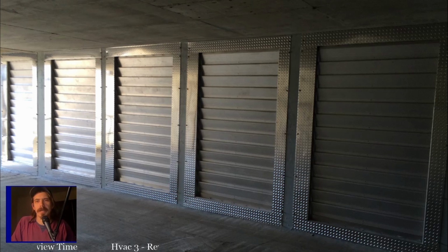So that circuit has to be energized for a split second before the time delay opens the circuit on the fan. That's generally how you can tell if the fan control is no good: you'll turn it on and the fan will just keep running. You don't see that initial bump and then it shuts off. As soon as you power that system on, the fan just runs.